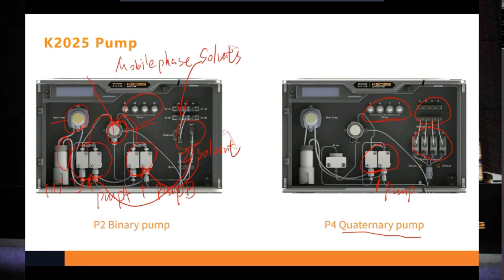It is called the purge valve. And this is also the place for the online filter. And then they will go to the mixer for better mixing. So the mixing part is after the pump head. So it is high pressure mixing. And for this place, it's after the pump. And for the quaternary pump, the mixing is in here.